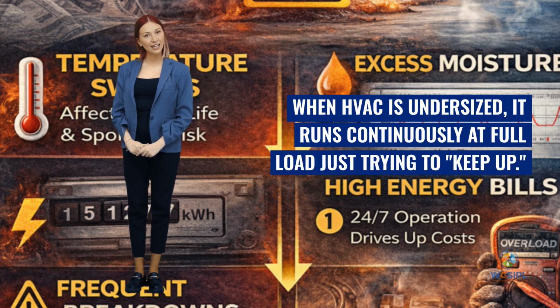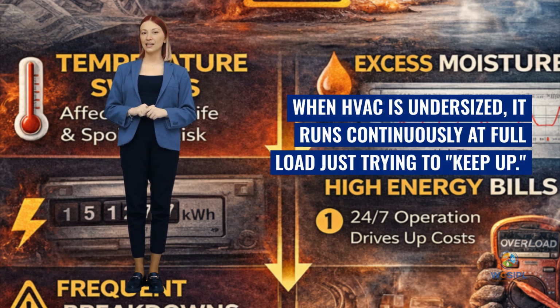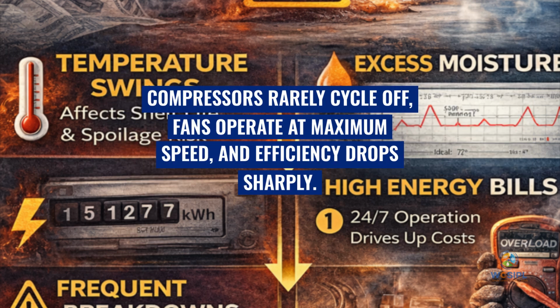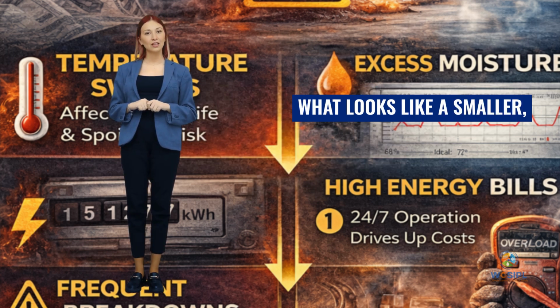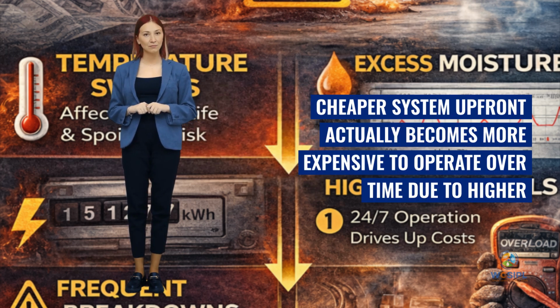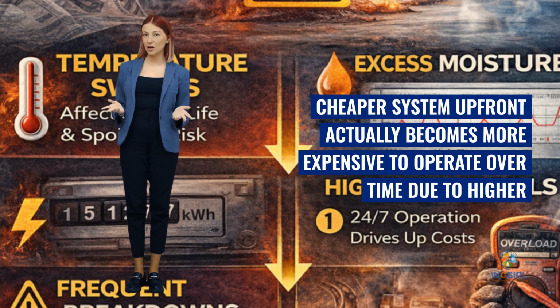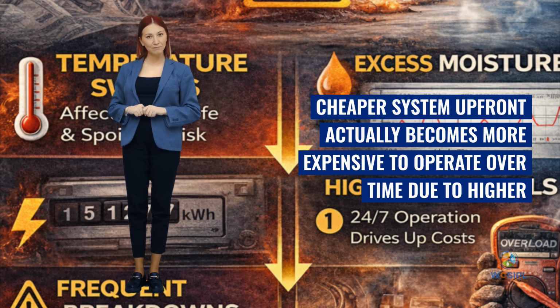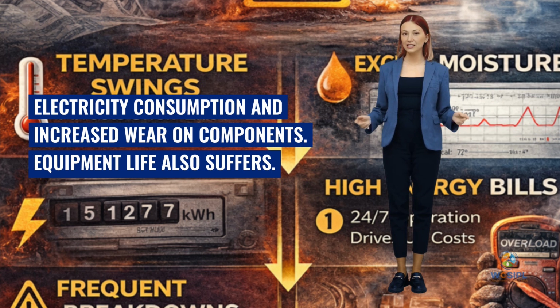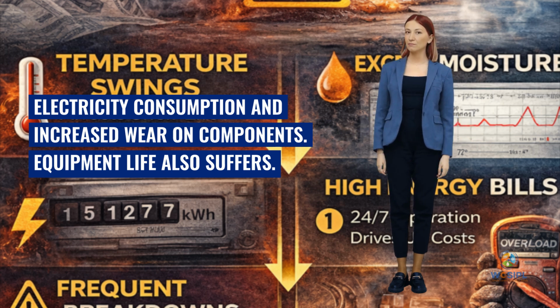When HVAC is undersized, it runs continuously at full load just trying to keep up. Compressors rarely cycle off, fans operate at maximum speed, and efficiency drops sharply. What looks like a smaller, cheaper system upfront actually becomes more expensive to operate over time due to higher electricity consumption and increased wear on components.